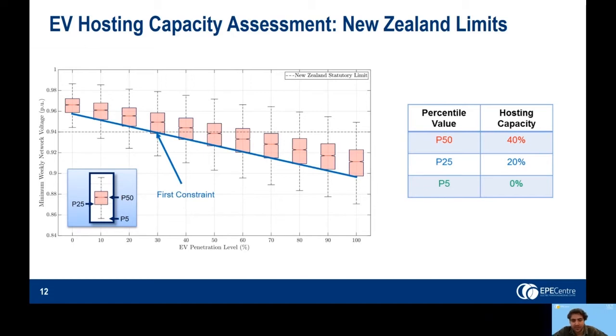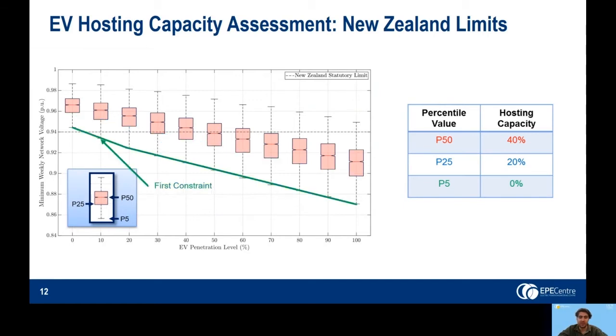Similarly, the 25th percentile hosting capacity can be calculated by drawing a line which connects the P25 values on each box plot, and I've shown that here in the blue. Here we can see that the first constraint occurs at the 30% penetration level, and therefore the 25th percentile hosting capacity is 20%. And finally, the 5th percentile hosting capacity can be calculated by drawing a line which connects the P5 values on each box plot. And here, the first constraint occurs at the 10% penetration level, and therefore the 5th percentile hosting capacity is 0%.